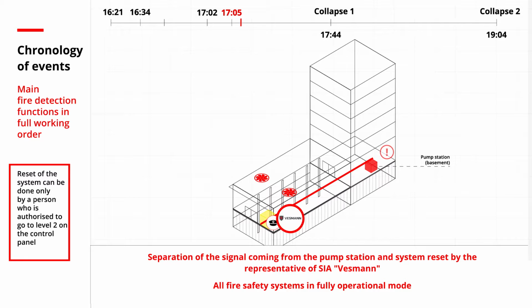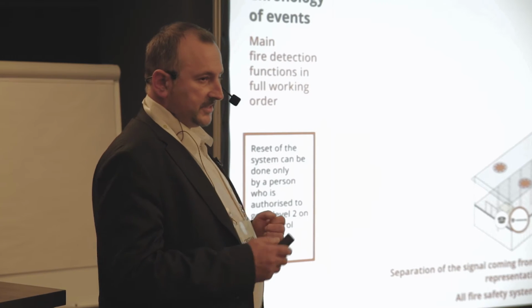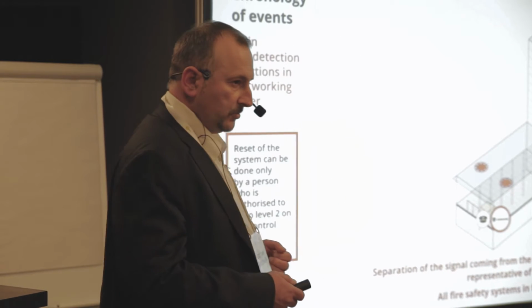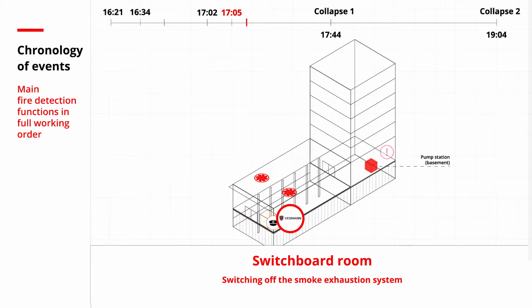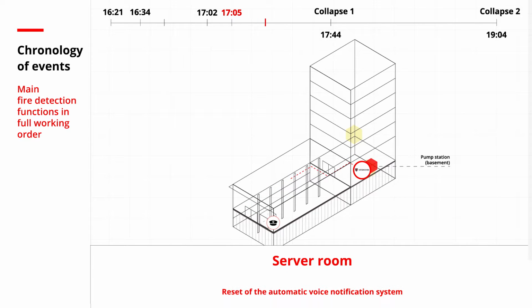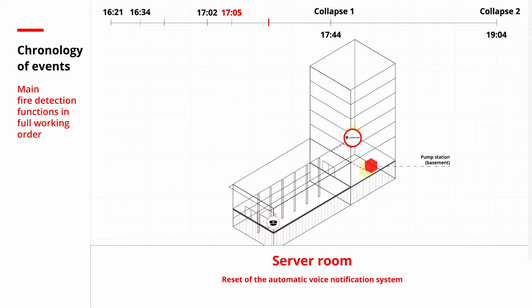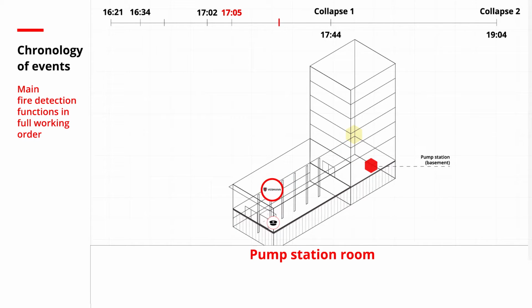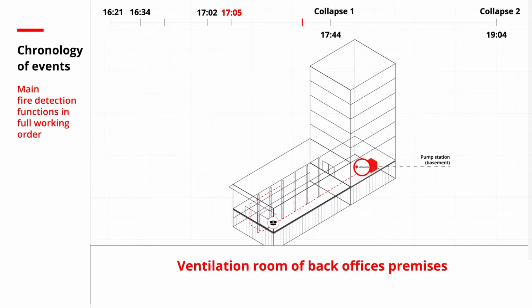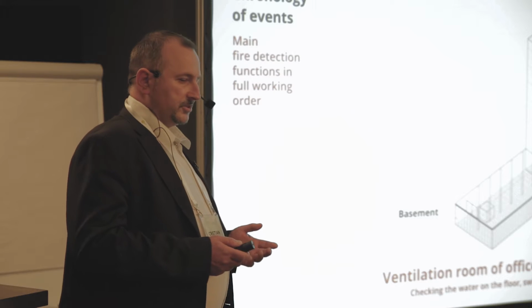First he separated the signals coming from the pump station, so he could reset the control unit in standby mode. And afterwards, he went to the switchboard room. He put off the smoke exhaustion system. Then he went to the server room. He reset the automatic voice alarm system. And last not least, he went to the pump station. And he was switching off the water pump. At this time, people came to him informing him that in an HVAC room and ventilation room, which is located nearby in the basement under the residential building, there is water coming out.